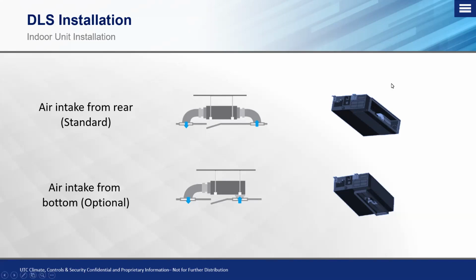Because if this is just resting on a steady platform and it's resting on the entire surface area of the bottom unit, you have no way of accessing that blower motor other than cutting into the ductwork, removing it, and then getting in the back side of the unit there. So something just to keep in mind, please make sure that you allow for proper service clearance on our indoor units so that you can access the fan motor. Otherwise, you're going to put yourself in an extremely difficult situation trying to access that fan motor, whether it's for cleaning or if the fan motor has decided to fail.